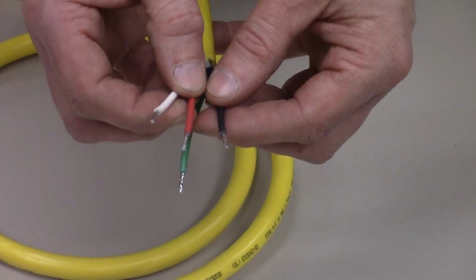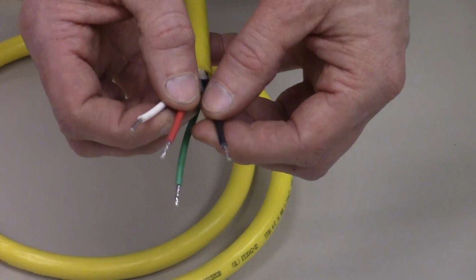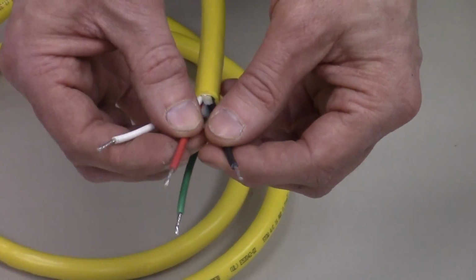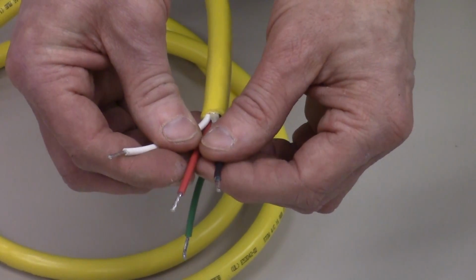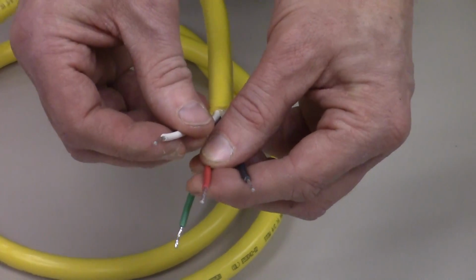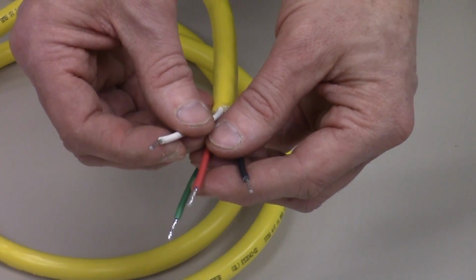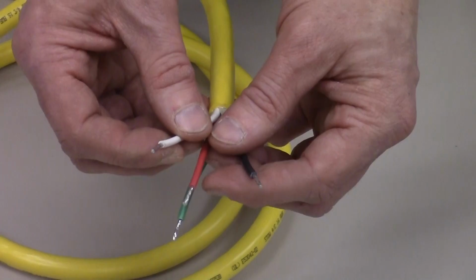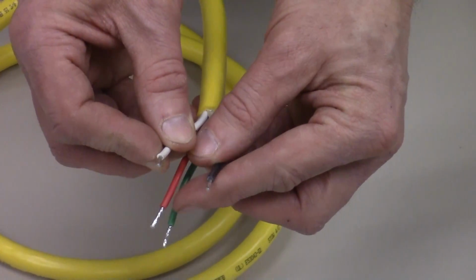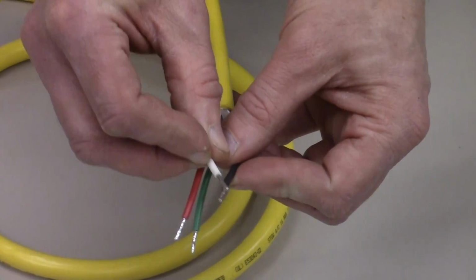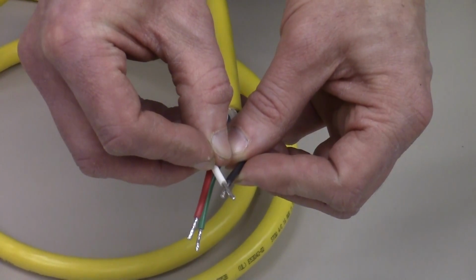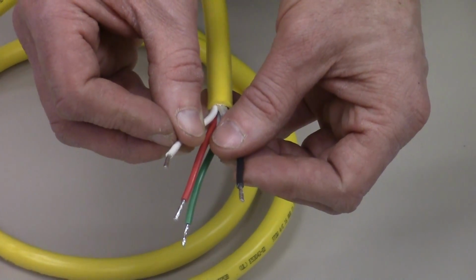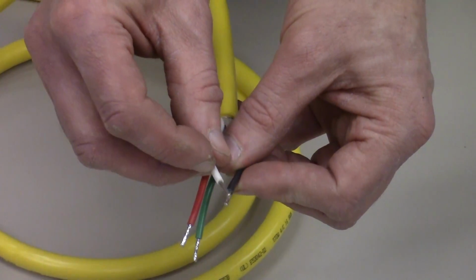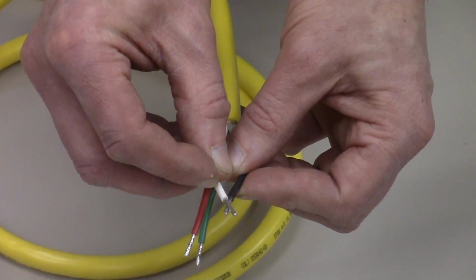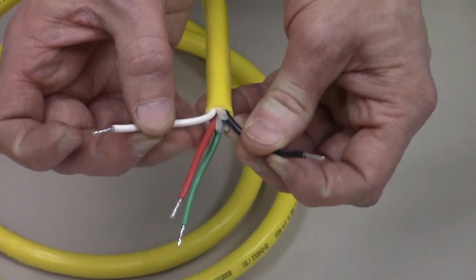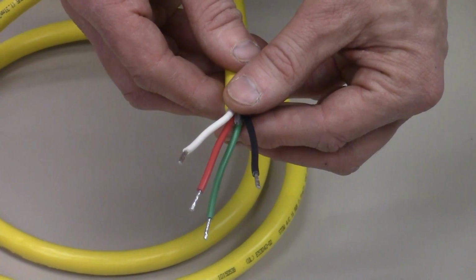In order to reprogram the 4 milliamp position, you're going to apply power to the red and black power lines of your ProStik. Once you have power on it, you will move your float to the desired position for the 4 milliamps. At that point, you're going to short the white program wire to the black wire for 3 seconds, break the connection for 3 seconds, and then short the wire again to the black wire for 2 seconds, break, and the new position has been programmed.